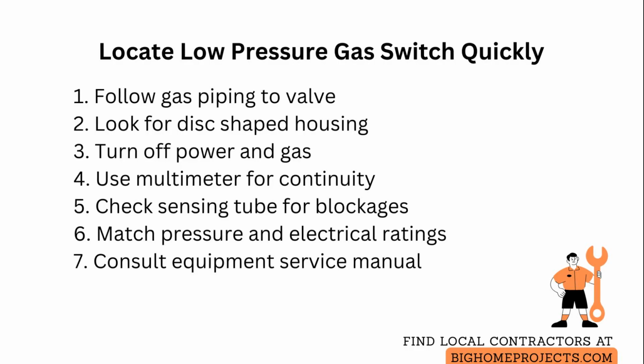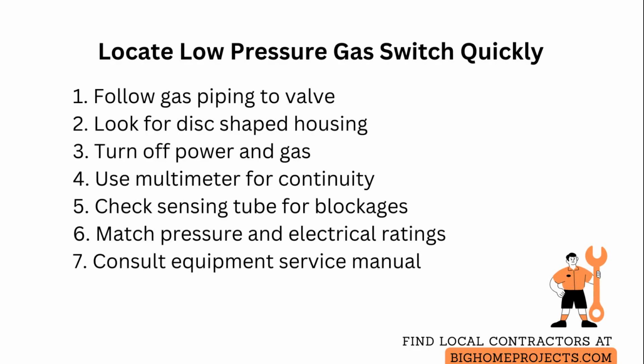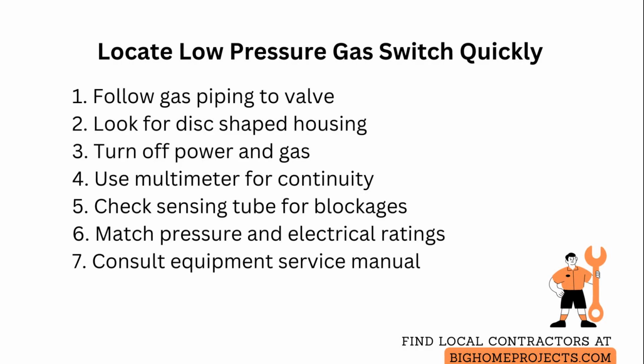If the switch is inline in a sensing tube, you may see a small nipple where the tube attaches. Check that tube for blockages, kinks, or oil and moisture, which can keep the switch from sensing correctly.